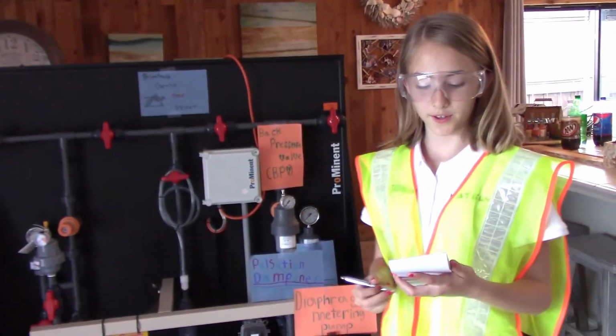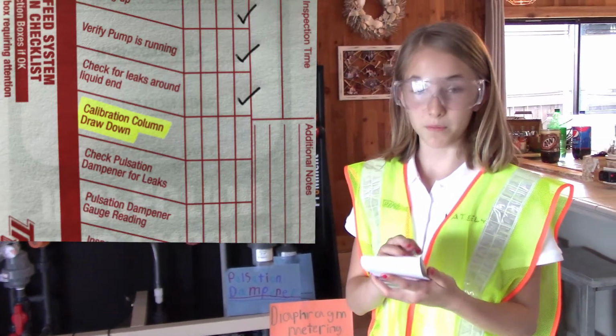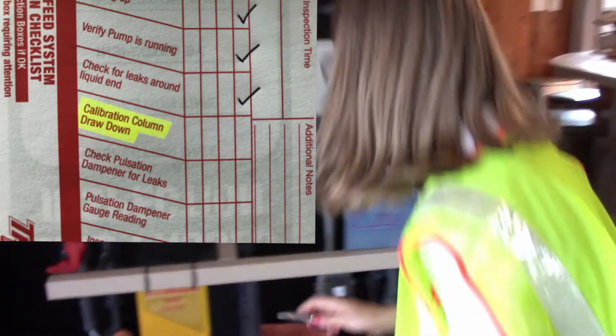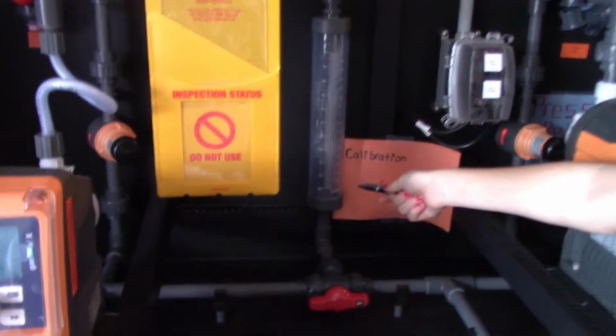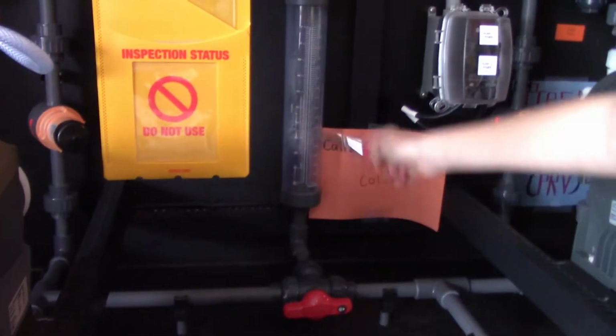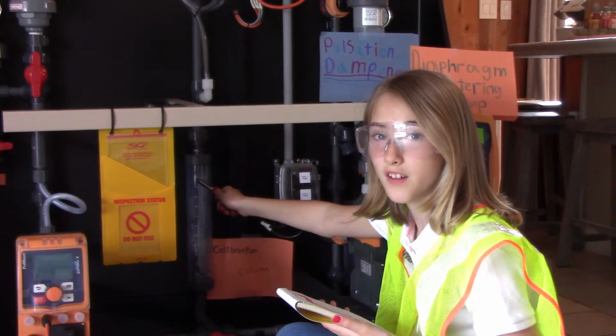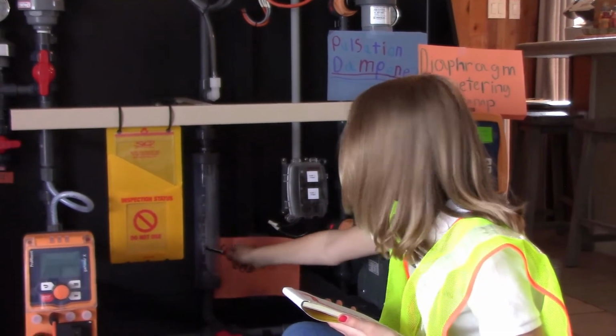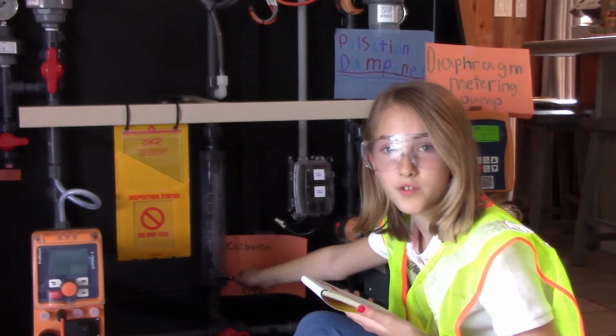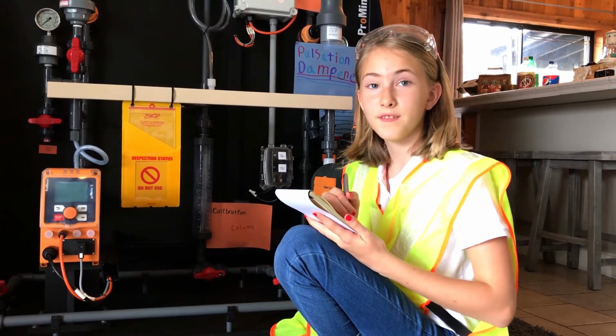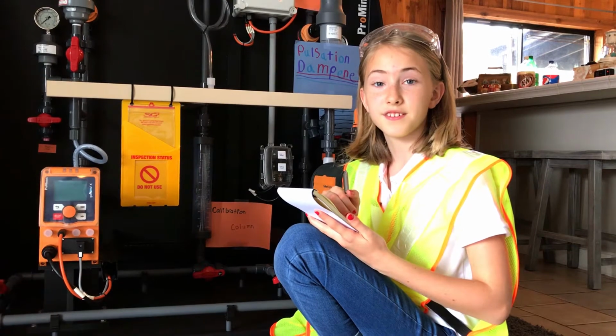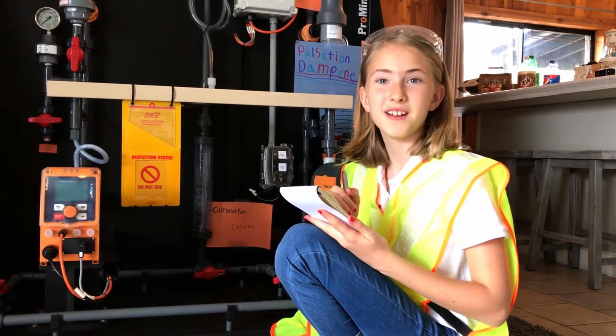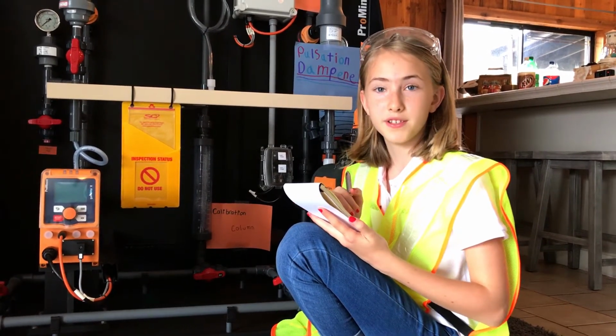The fourth thing we're going to look at is the calibration column drawdown. As you can see, here is the calibration column. We're going to open the valve and let it fill up to 0, then close the main suction valve. Let the pump discharge the fluid from the calibration column. Time for 30 seconds to verify the flow amount of the calibration column and metering pump should be the same measurement.